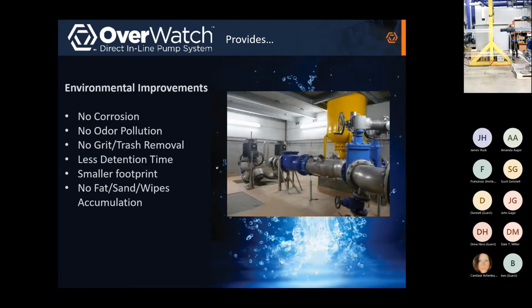And then environmental improvements, right? So there is no corrosion of the system. We use all stainless steel parts, so we don't have to worry about erosion. You don't have to worry about the corroding of the basin, whether it be concrete or some other material that H2S gas would eat up over time, right? And then you have to worry about the basin leaching. We don't have to worry about that because we've got rid of the wet well. Again, no odor pollution, odor compression systems are gone. Grit and trash removal, we're going to show you how that manages it differently, right?